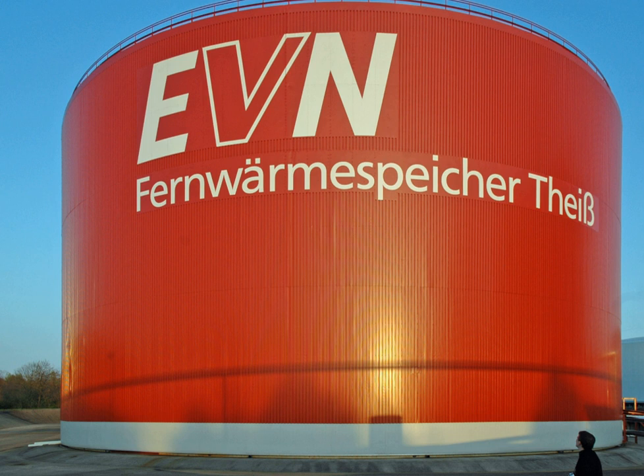In a temperate climate like that of the Netherlands, an average low-energy household requires about 6.7 gigajoules per winter. To store this energy in water at a temperature difference of 70°C, 23 cubic metres of insulated water storage would be needed, exceeding the storage abilities of most households. Using salt hydrate technology with a storage density of about 1 gigajoule per cubic meter, 4 to 8 cubic metres could be sufficient. As of 2016, researchers in several countries are conducting experiments to determine the best type of salt or salt mixture. Low pressure within the container seems favorable for energy transport. Especially promising are organic salts, so-called ionic liquids, which are less problematic in terms of limited global resources and less corrosive than most halides and sodium hydroxide, and not negatively affected by CO2 contaminations.